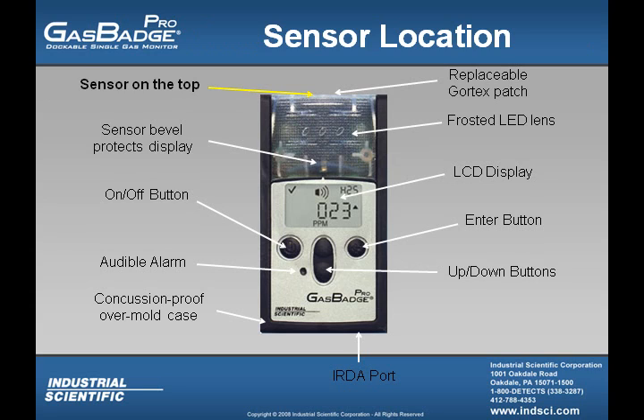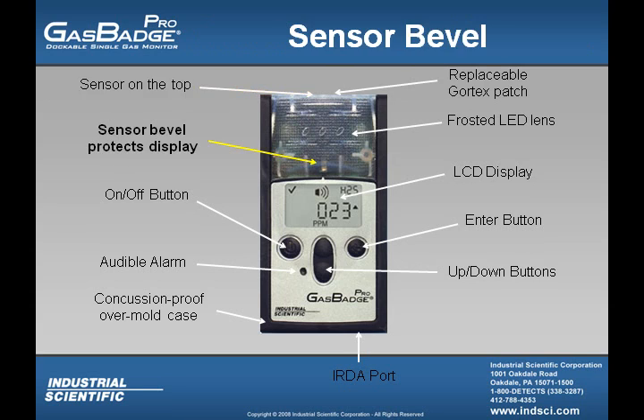At the top of the instrument is the sensor. With the sensor located at the top of the instrument, we are able to put the GasBadge Pro in a place like a shirt pocket. Industrial Scientific has also gone to such lengths as beveling the sensor, so that the display is protected from accidental bumps.